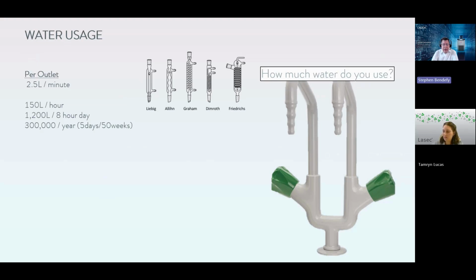How much water are we actually talking about? Well, we did some studies, and typically one tap in the laboratory will consume approximately 2.5 litres per minute, delivering 2.5 litres per minute. That equates to approximately 150 litres an hour, which in an 8-hour day is around 1,200 litres.